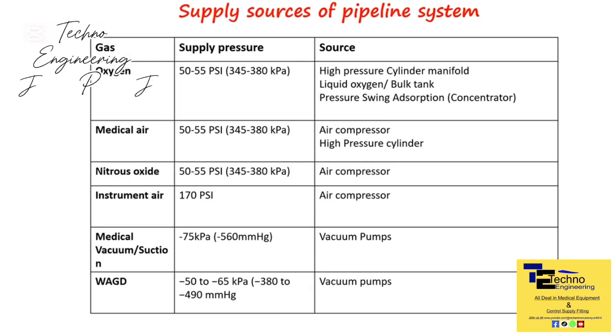Instrument air powers surgical tools and is produced on-site using an air compressor. Instrument air is now a popular substitute for nitrogen, operating at pressures around 170 psi. The medical vacuum system in hospitals aids suction equipment by utilizing vacuum pump systems that exhaust to the atmosphere. While vacuum levels may vary along the pipeline, they are typically maintained at around -75 kilopascals or -560 mm of mercury.